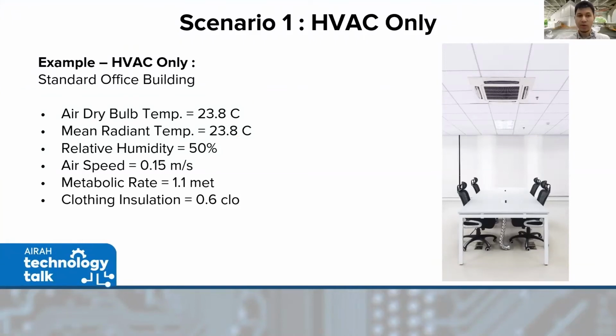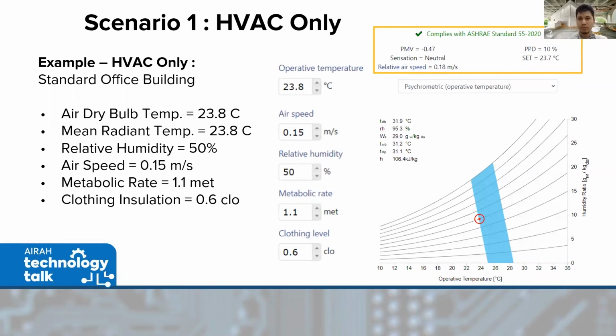Scenario 1, HVAC only, a standard office building. These are the thermal comfort inputs: 23.8 degrees air temperature, 23.8 degrees radiant temperature, relative humidity 50%, airspeed 0.15 meters per second, metabolic rate 1.1 met, and clothing insulation 0.6 clo. When we put this into the CBE thermal comfort tool, it says yes, we comply with ASHRAE standard 55. All is good, conditions pass.